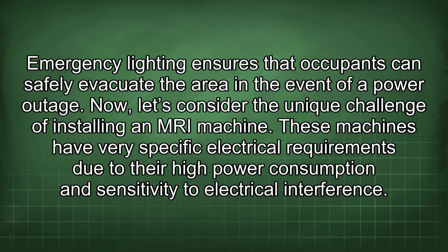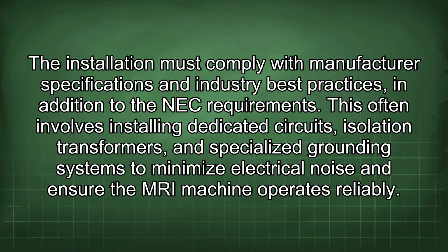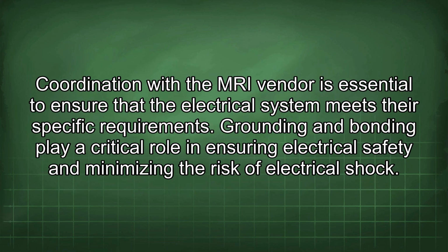Now let's consider the unique challenge of installing an MRI machine. These machines have very specific electrical requirements due to their high power consumption and sensitivity to electrical interference. The installation must comply with manufacturer specifications and industry best practices in addition to the NEC requirements. This often involves installing dedicated circuits, isolation transformers, and specialized grounding systems to minimize electrical noise and ensure the MRI machine operates reliably. Coordination with the MRI vendor is essential to ensure that the electrical system meets their specific requirements.